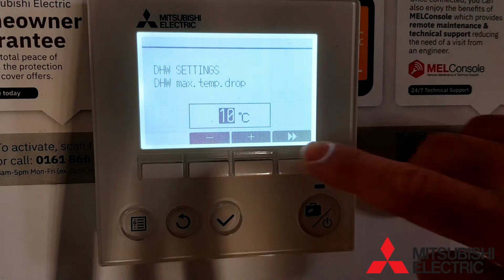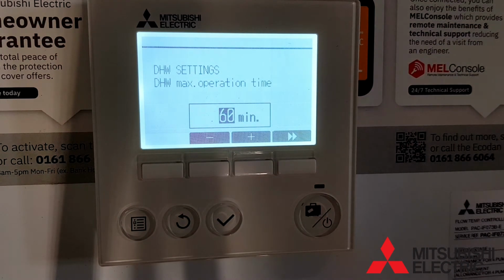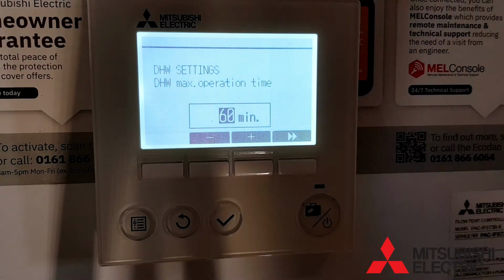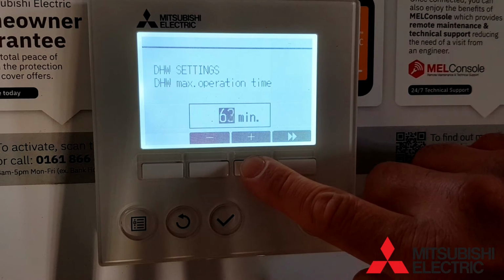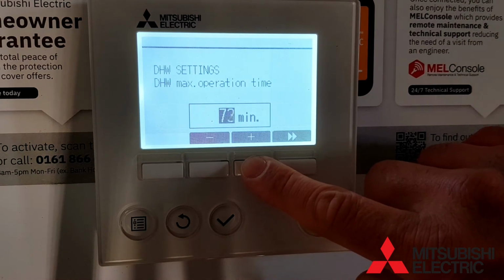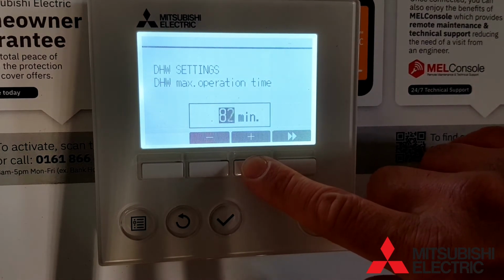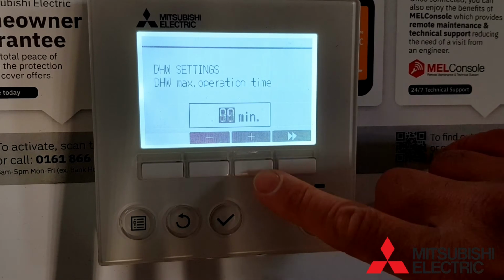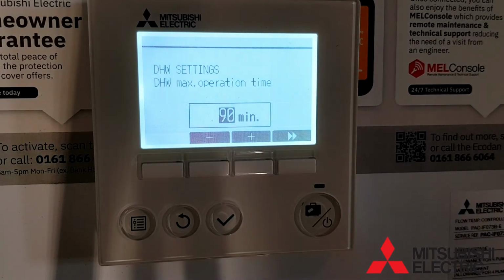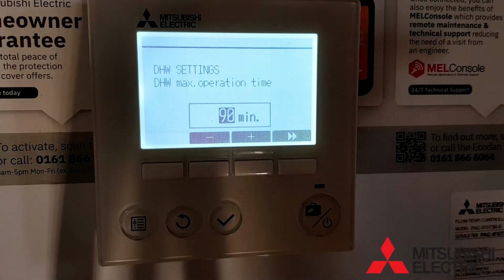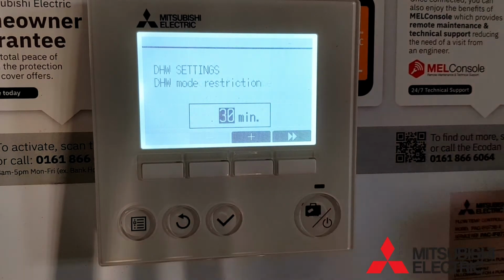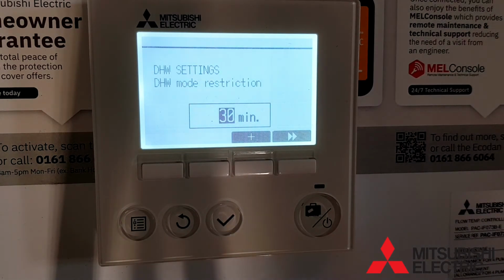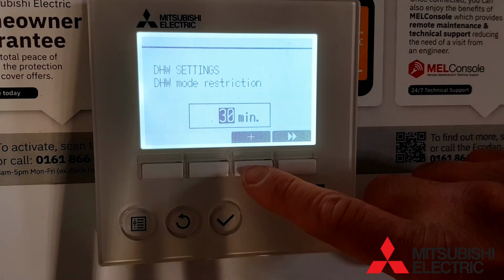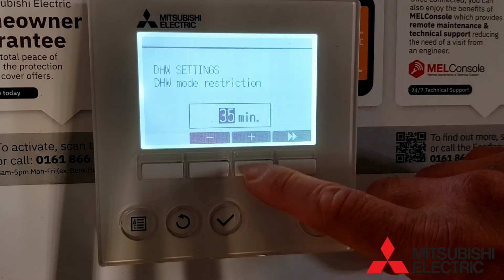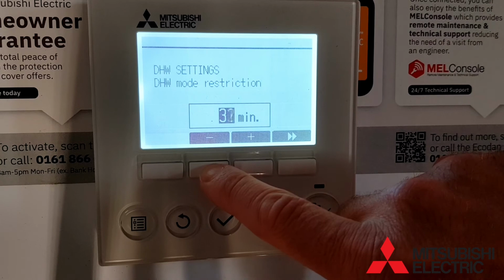This next section is the maximum operation time. This should be set higher than the amount of time it took to heat the cylinder from scratch on the first heat up cycle. 90 minutes should be sufficient. The next screen is the hot water mode restriction. This is the amount of time it must wait in between hot water cycles to stop it from constantly cycling on and off in hot water.